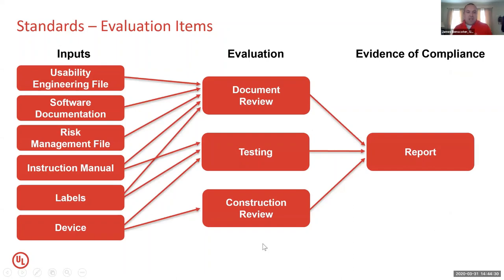When we do an evaluation within these documents, you'll see there's a lot of inputs and there's a lot of things that feed into this process. But the key I wanted to point out in this little picture here is that the evaluation process doesn't need to be a serial process. A lot of people tend to think the process needs to be serial. There are some contingencies within this process. For example, there may be certain test conditions that the standard requires that you can't determine until you have done a document review of the risk management file, or you may not understand how the device complies with a specific construction requirement until you've reviewed some software documentation and had that discussion. So these processes can be done in parallel, but they do require a lot of interaction between parts. It's a lot of different items coming together to get you to the end point where you have one specific document that provides the relevant evidence.